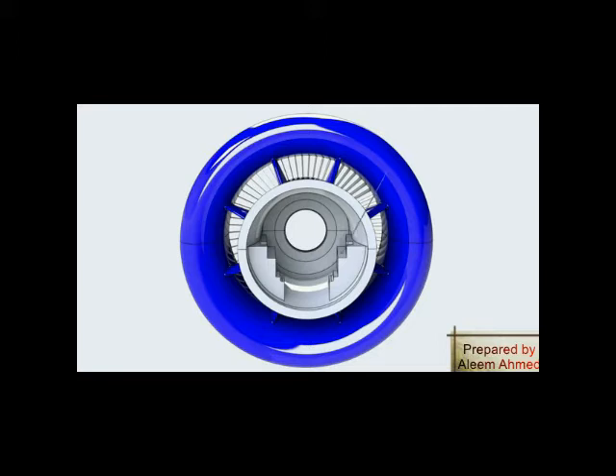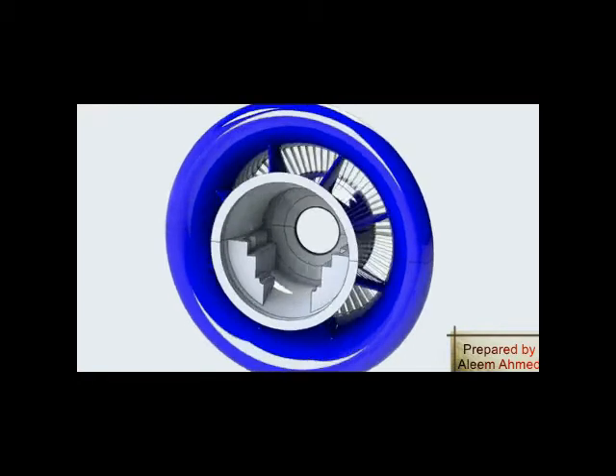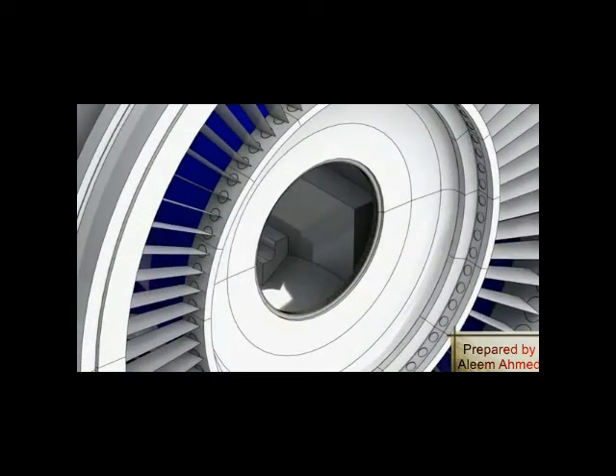The lower half of the bell mouth provides support for bearing number one. A stationary labyrinth seal is installed at the aft end of the inlet casing to prevent suction of contaminants into the compressor.